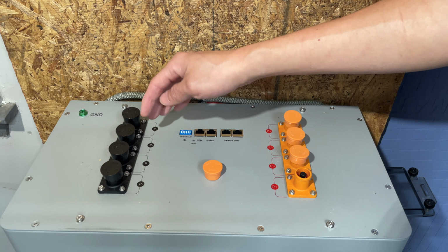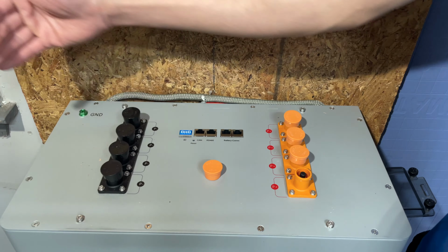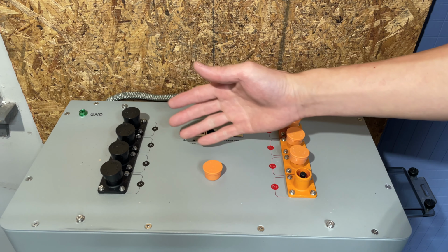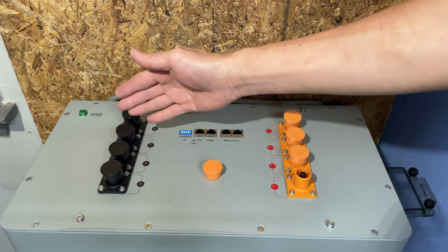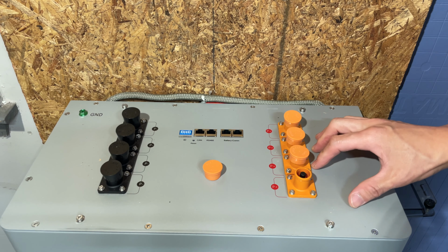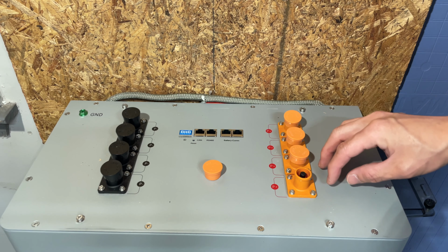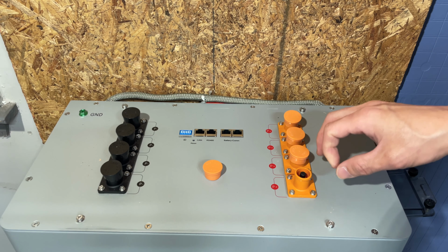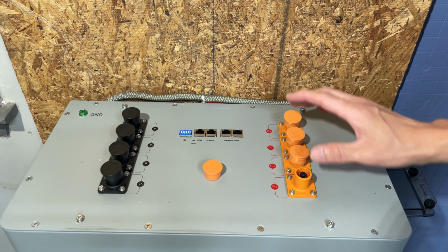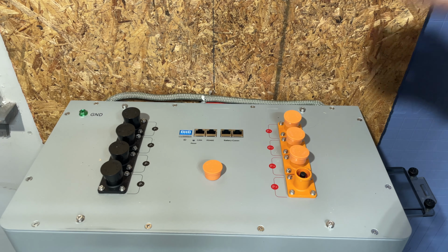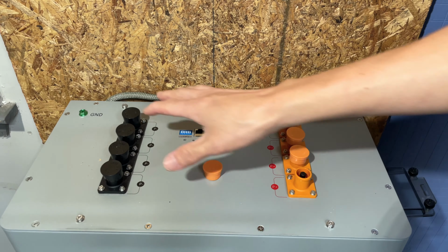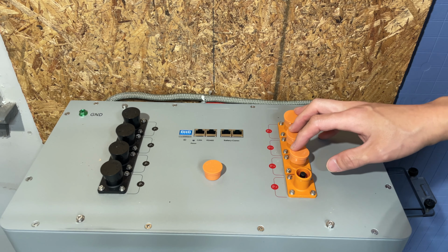The reason for that is mainly so you can parallel other batteries to this, and you can also connect the inverter here. There's a bus bar inside connecting them all together, rated for up to 600 amps. So you won't have a limitation trying to use these batteries with, say, two 6000 XPs or anything like that, because it's rated for it.